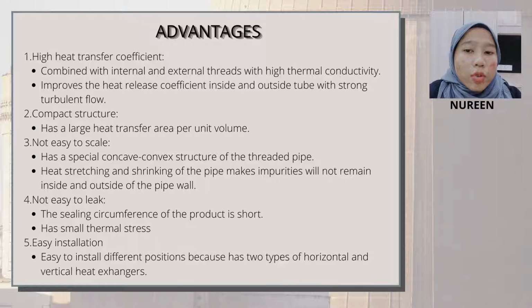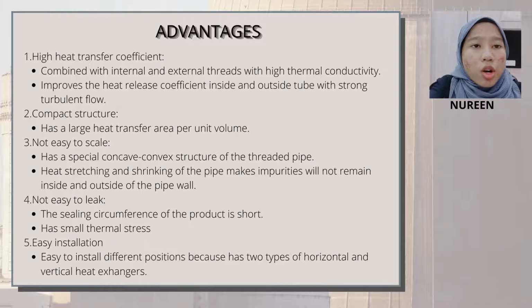The concept has been around for well over 100 years, for example the steam engine boiler. Because of their simplicity and versatility, they can be produced at a low cost even in small quantities. Because most designs are easy to disassemble, they are suitable for applications that require frequent maintenance and service, such as in maritime settings. So the advantage of shell and tube heat exchangers, the first one is high heat transfer coefficient.